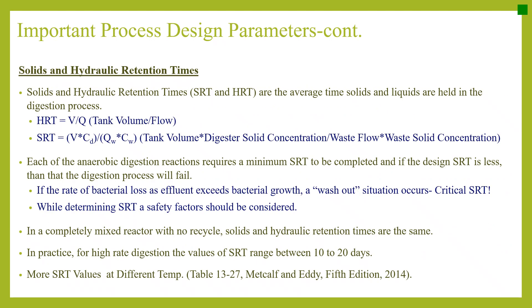Solid and hydraulic retention times are the average time solids and liquids are held in the digestion process. HRT can be calculated as tank volume divided by flow, and SRT can be calculated as tank volume multiplied by digester solid concentration, divided by waste flow multiplied by waste solid concentration. Each anaerobic digestion reaction requires a minimum SRT to be completed. If the design SRT is less than that minimum, the digestion process fails — this situation is called washout, and that minimum SRT required to prevent it is known as the critical SRT.